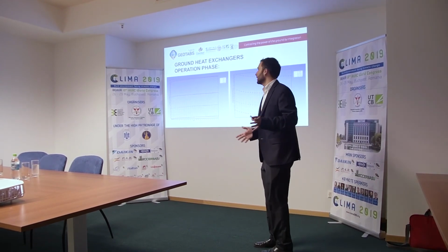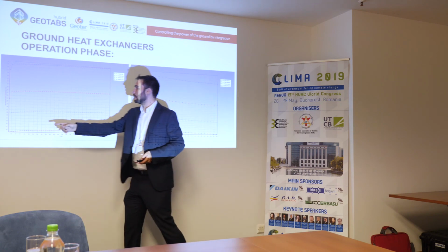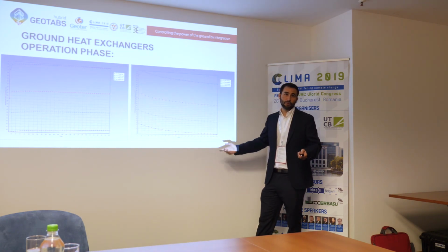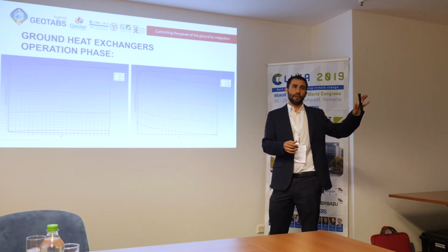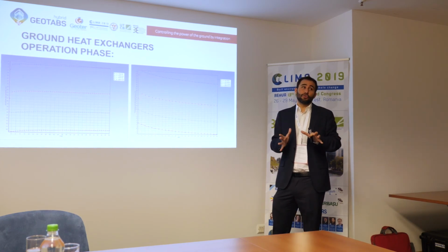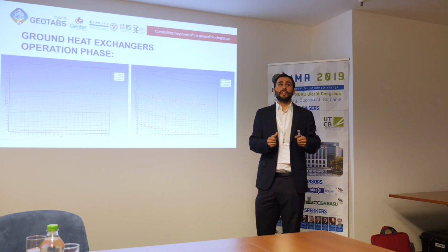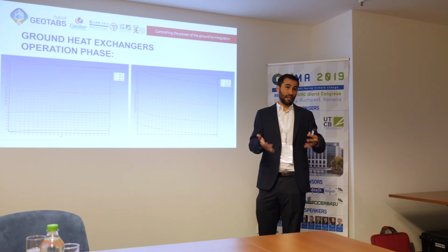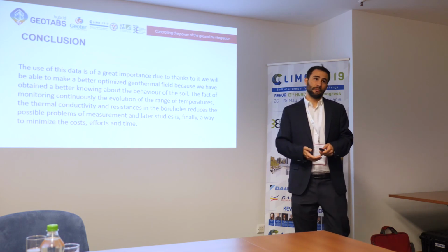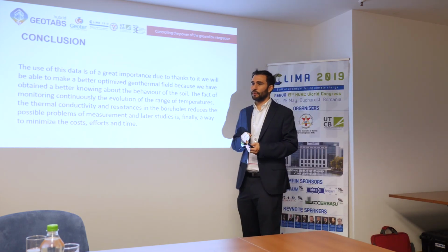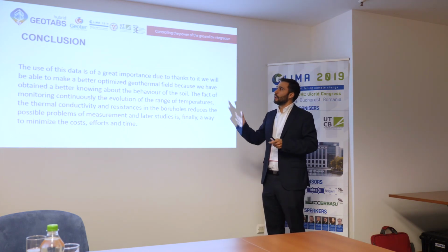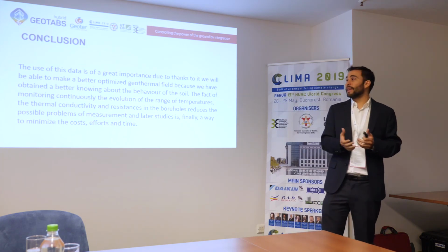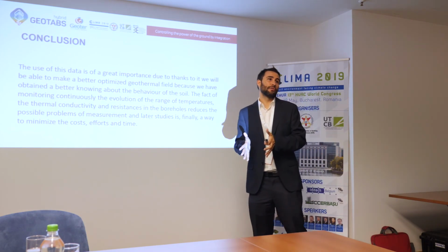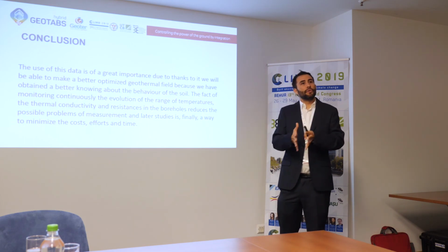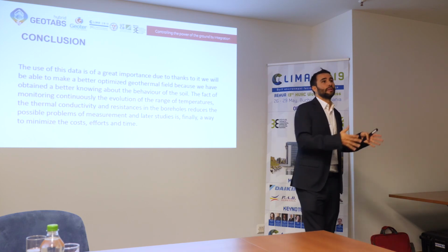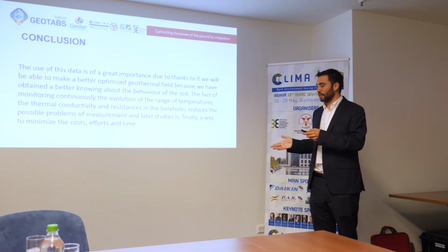So finally, only to say that, for example, this is a real simulation of a building, but reality is different later. So it's very important to see the differences between the first simulation and the real use of the building, so we have to be able to respond to these changes. Okay, and the conclusion is that with this system, with the enhanced geothermal response test, and with the control of the operation phase, we have a lot of data, and we can use this data to improve the sizing of the borehole or the operation of the borehole, which is very important because it's a key module of a hybrid GEOTABS building, and it's very important to reduce the cost and reduce the energy that we are going to use in the building.